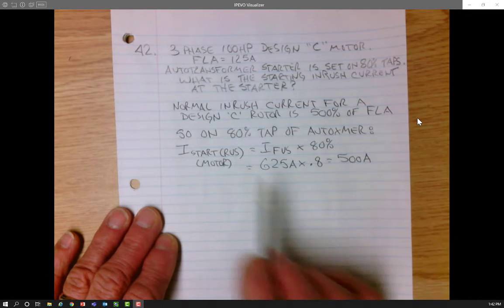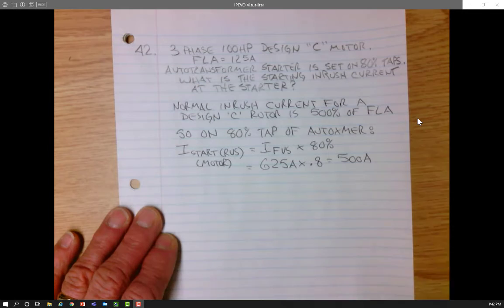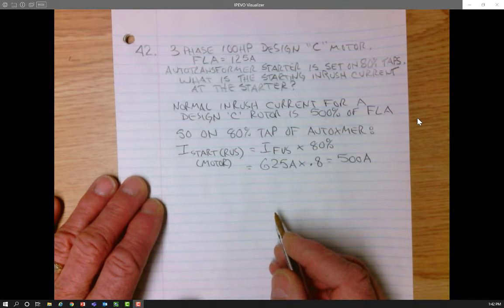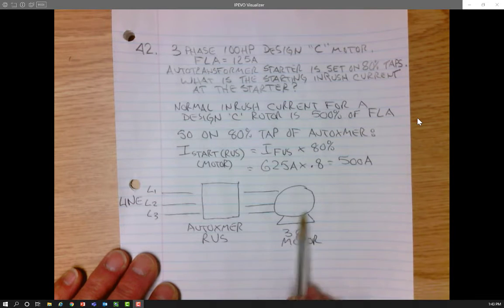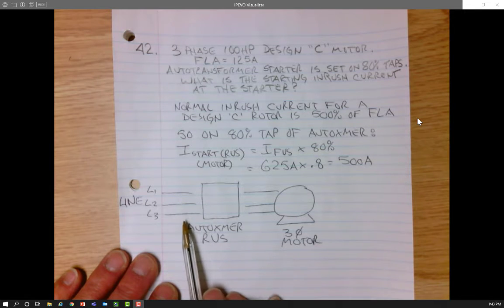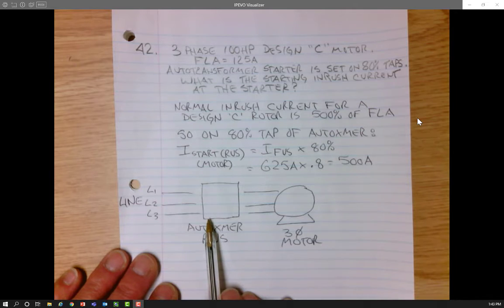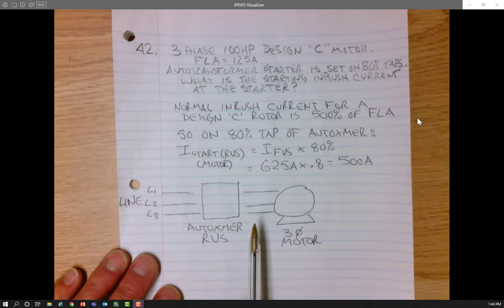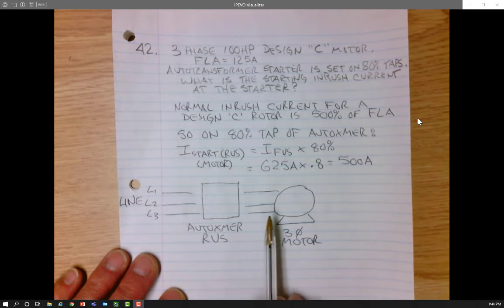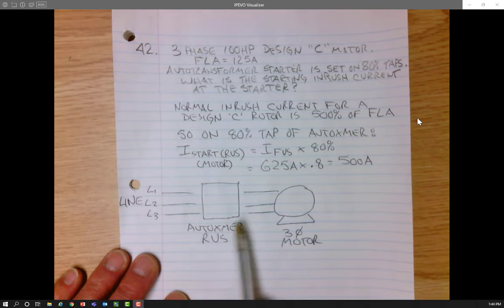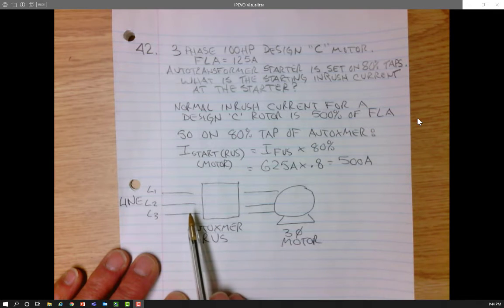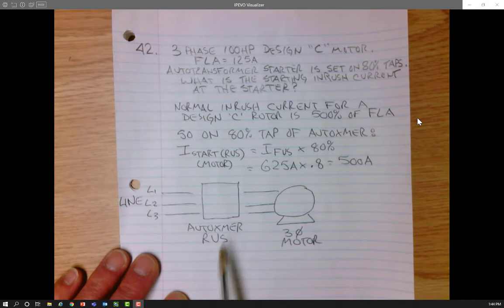instead of 625. But in the question, they're asking, what is the starting inrush current at the starter? And a way to think of this is, if I drew a real quick diagram of what it would look like, what the question is asking for is not what the current's reduced to at the motor, but what the current is reduced to on the line side of the starter itself. And auto transformer reduced voltage starters give us a second reduction on the line side because we have the 80% tap we're using, so we're using only 80% of the windings of that auto transformer to feed voltage to that motor. And we also have a transformer ratio where if the voltage goes up on this side of the auto transformer, then the current's going to go down going back to this side to keep the volt amps primary equal to the volt amps secondary of our auto transformer.